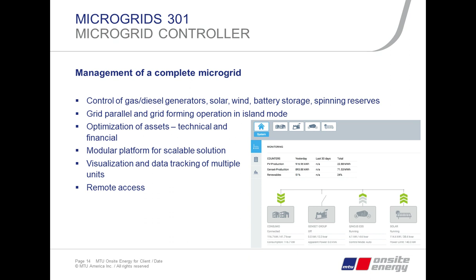Let's break it down in terms of the control architecture to show how this modular concept works. On the primary side, that's very much the genset controllers still, so we have to do typical genset things like stabilizing voltage and frequency. We offer plug and play capability for adding different resources, share active and reactive power across units, and want to mitigate circulating currents and other electrical issues. That's the primary control function.